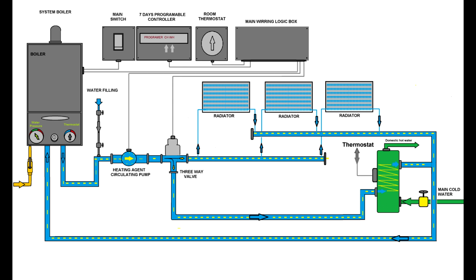Then you will open the domestic water and fill the domestic water tank. Please do not make the mistake of confusing the closed circuit of the heating system with the domestic water. Can you see inside? It's a spiral in the tank which will heat the domestic water, so they do not directly communicate. Alright? So once we clarify this, you will leave that domestic water on all the time.